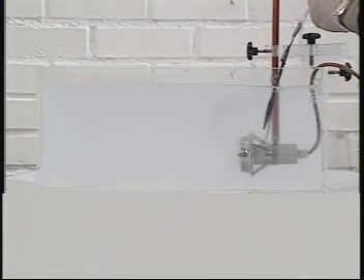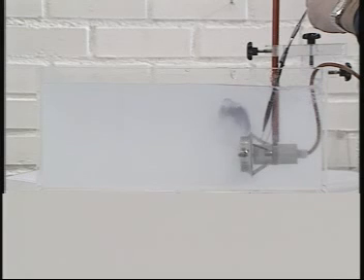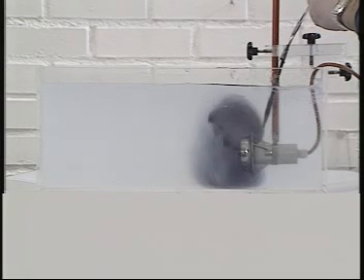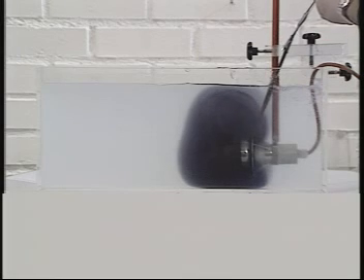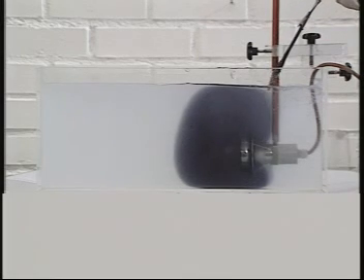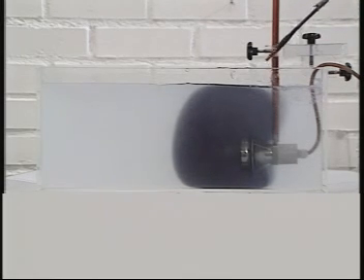Also, if yield stress is too high, making the mixer undersized, the flow in the tank, and especially the backflow to the mixer, will be weak. This may also cause overheating, because circulation around the motor housing will be insufficient.